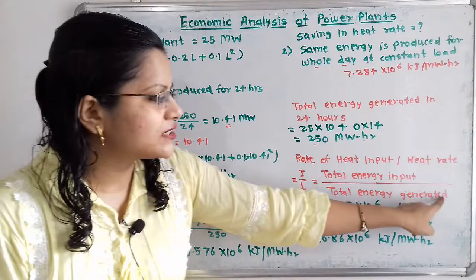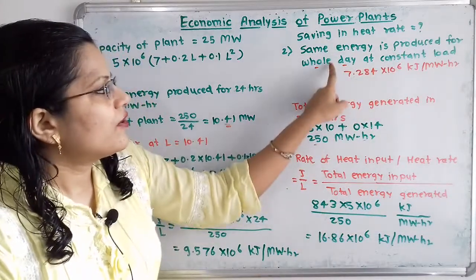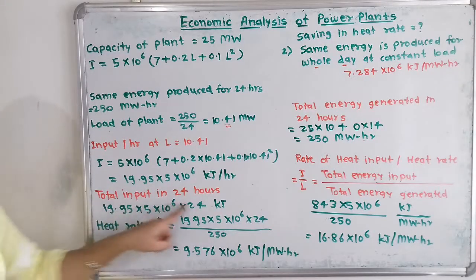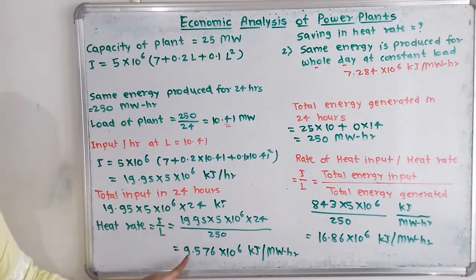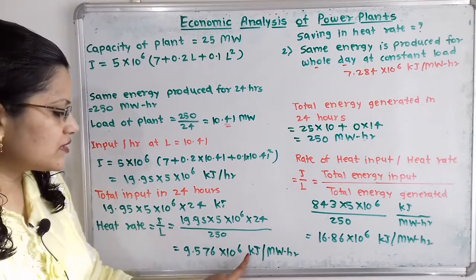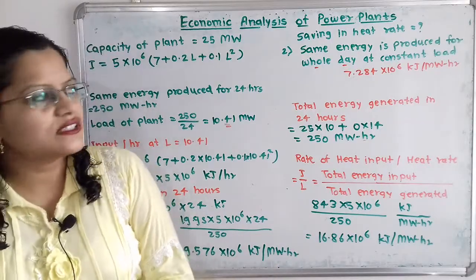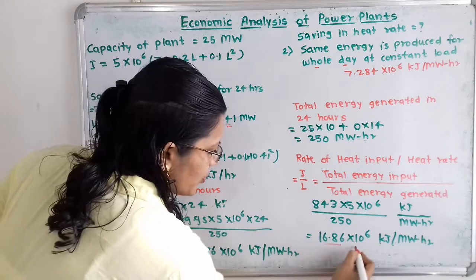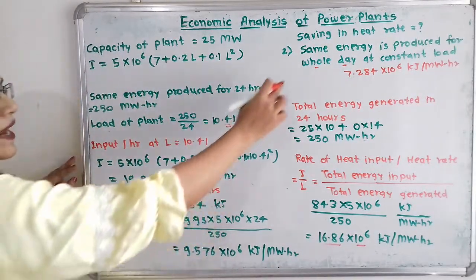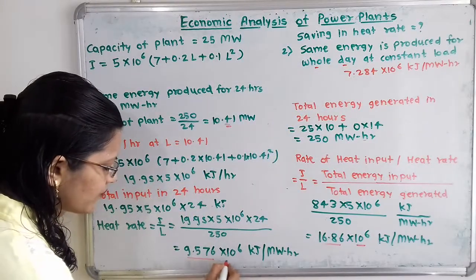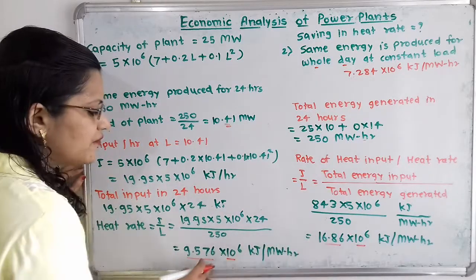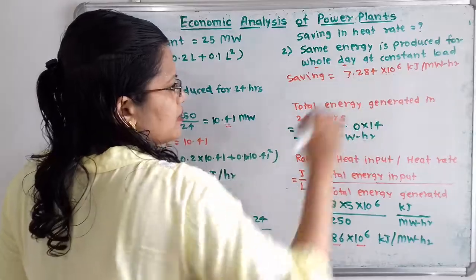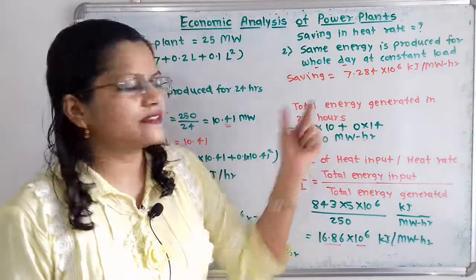The total energy generated remains 250 megawatt-hour. So the heat rate for the second case = (19.95 × 5 × 10^6 × 24) / 250 = 9.576 × 10^6 kilojoule per megawatt-hour. The saving in heat rate = 16.86 × 10^6 − 9.576 × 10^6 = 7.284 × 10^6 kilojoule per megawatt-hour. This is the answer to the second question.